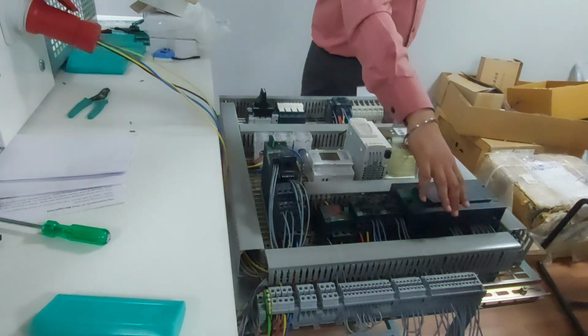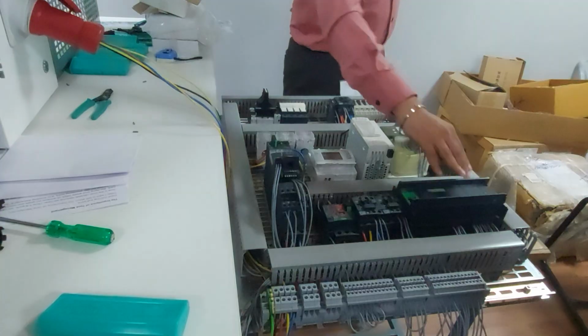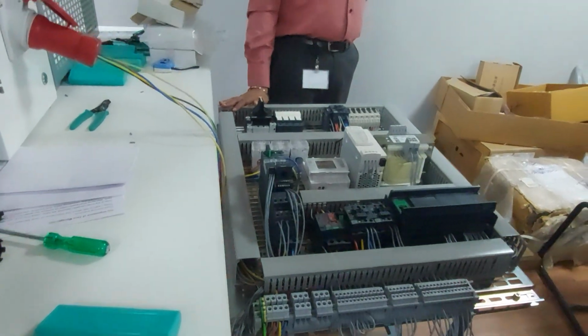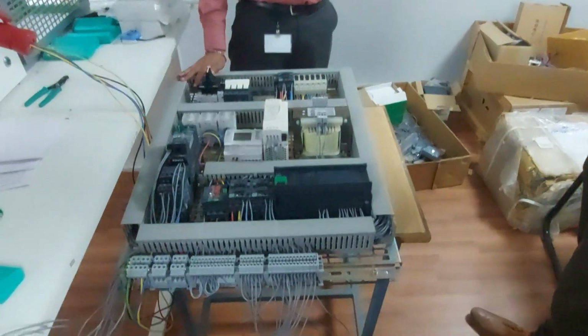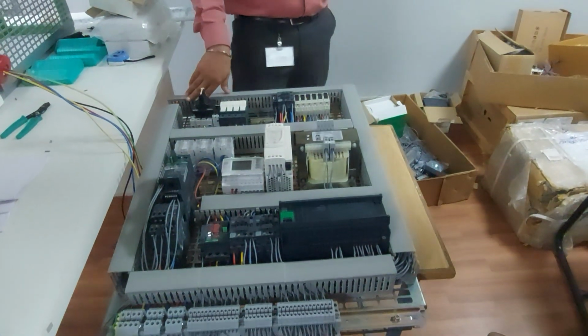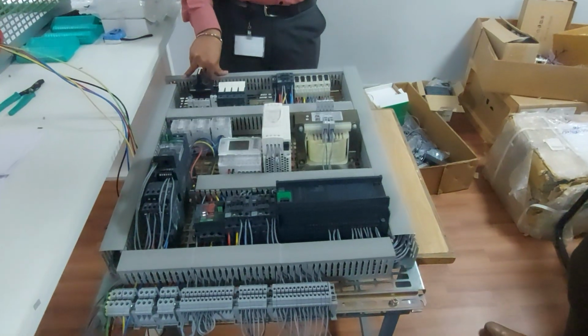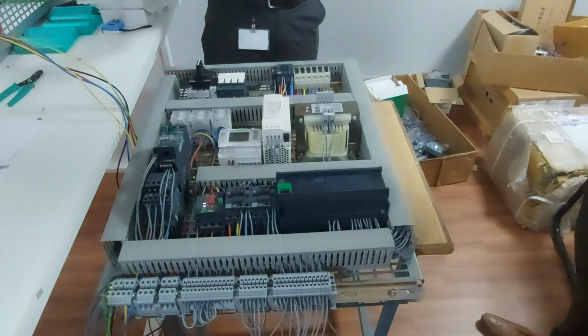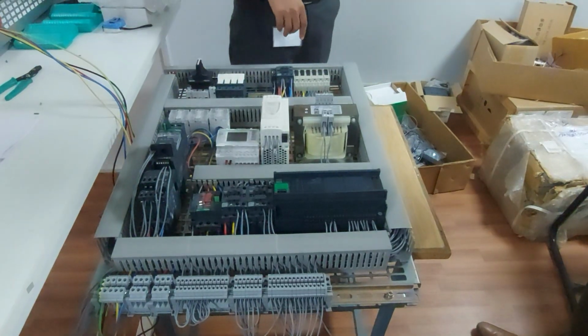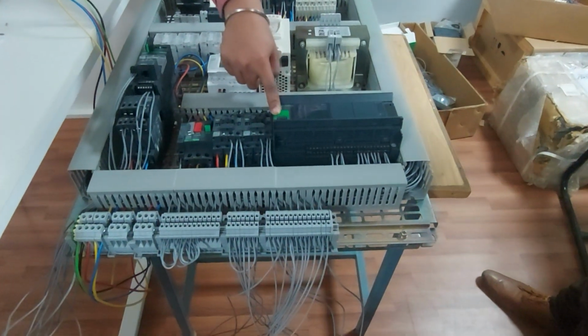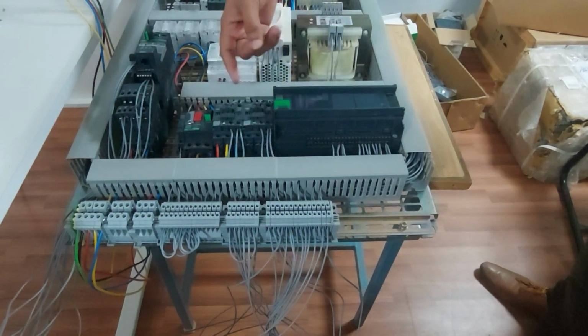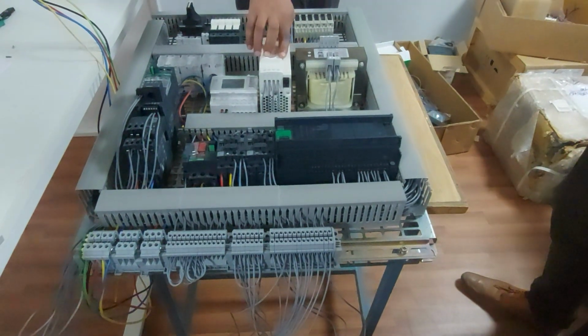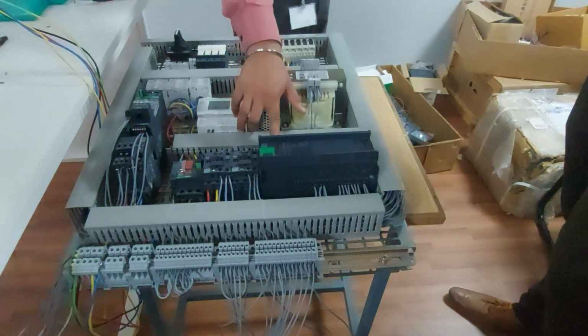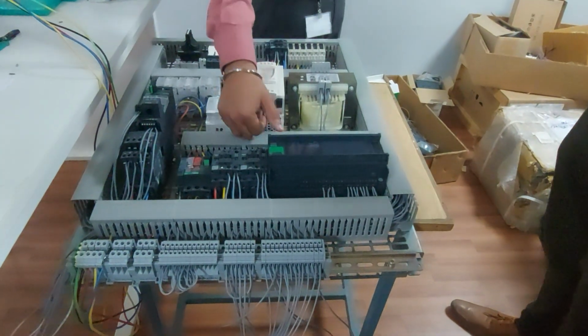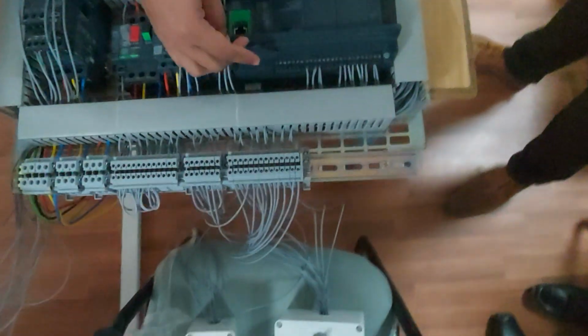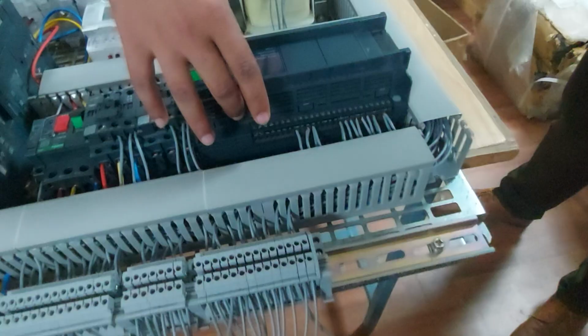So this is about a PLC, and this is a TM241 CE40R. The part number of this PLC is TM241 CE40R. Here M241 is the part number. C and E indicate communication. C here is communication for Ethernet as well as Modbus. The green color indicates TCP/IP, that is Ethernet communication protocol, and we have one more communication protocol, that is serial communication. I told you about serial communication yesterday. So you can connect an energy meter or different devices. We have one RJ45 port here, and here we can see D0, D1, which is serial.